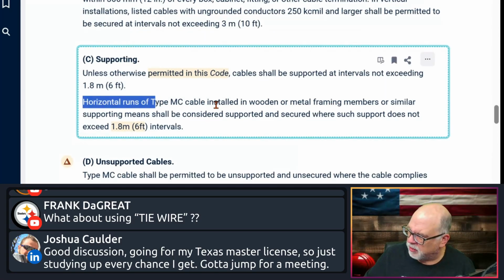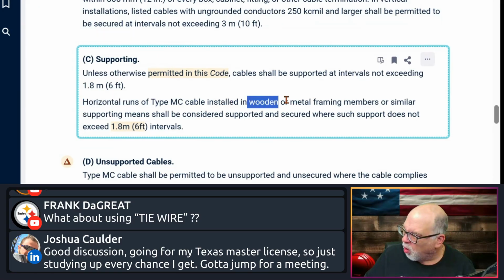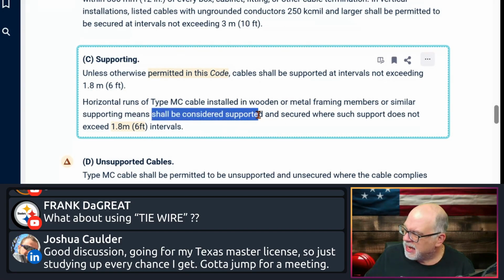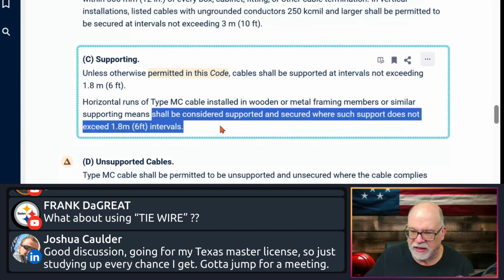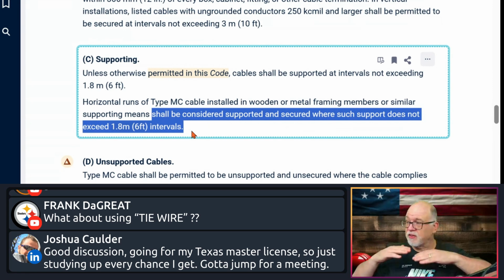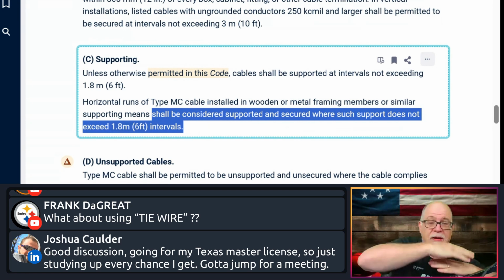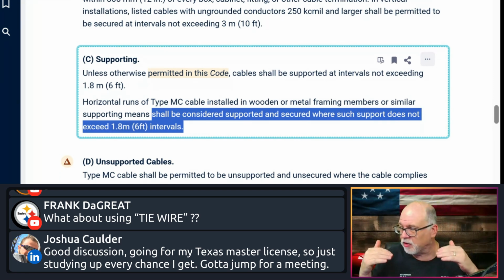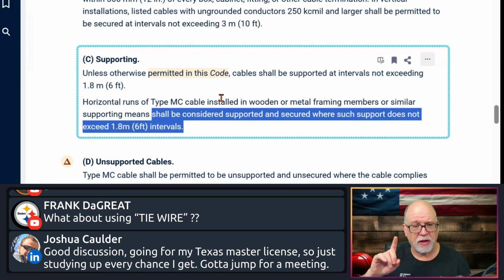runs of MC cable installed in wood, and notice installed in wood, or in metal framing members or similar supporting means shall be considered supported and secured where such support does not exceed 6 feet. Okay, so is it considered supported if I run it over framing members? Absolutely, it's considered supported, okay, horizontally, right? That type of scenario. Still has to be secured, but it's considered supported.